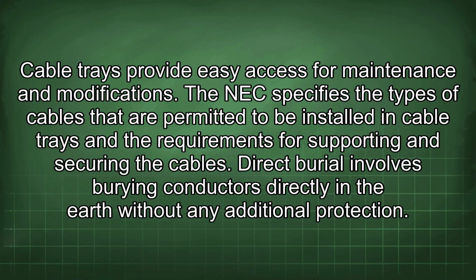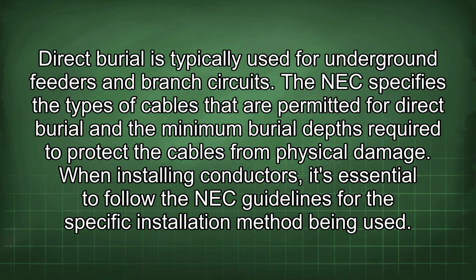Direct burial involves burying conductors directly in the earth without any additional protection. Direct burial is typically used for underground feeders and branch circuits. The NEC specifies the types of cables that are permitted for direct burial and the minimum burial depths required to protect the cables from physical damage.